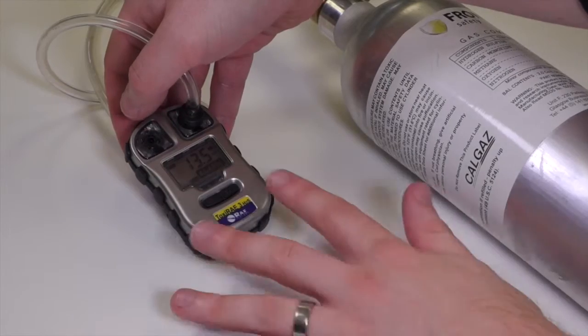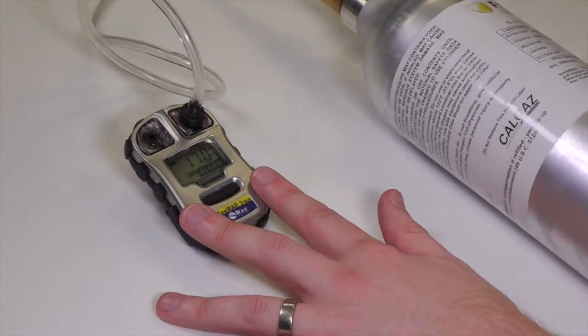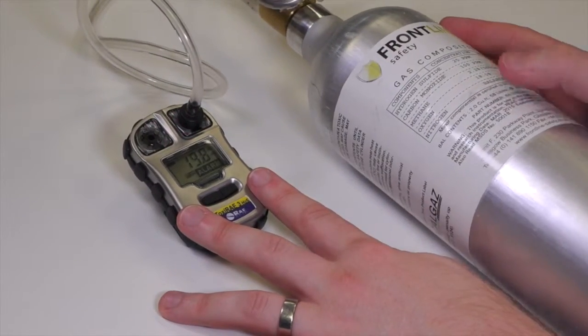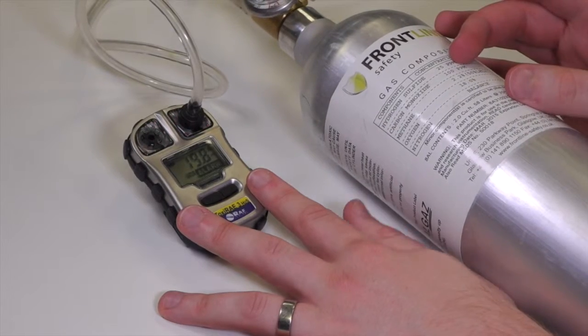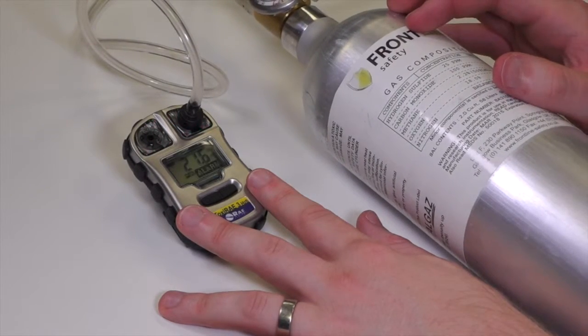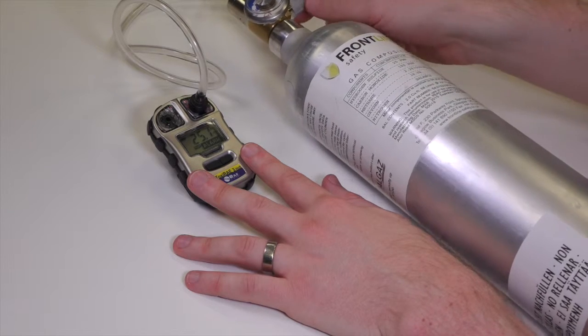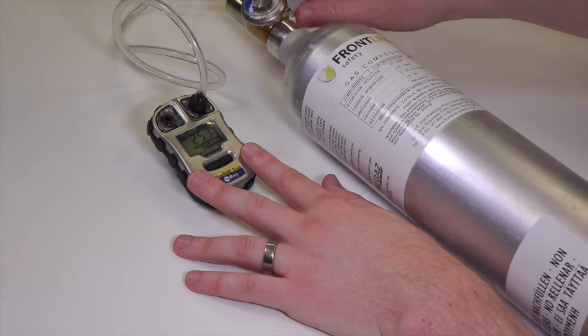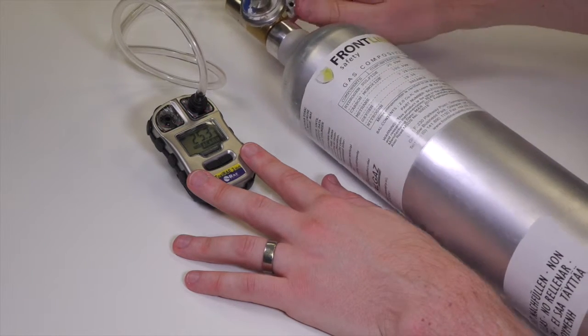So we know there that it's responded to the gas and we should see that reach 25 ppm. 25 ppm in the cylinder, we're looking for that there on screen. And that's it, reached 25 ppm, so the unit's responded as we would expect.